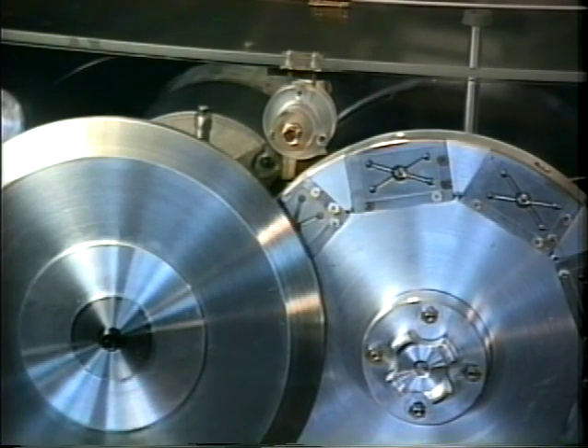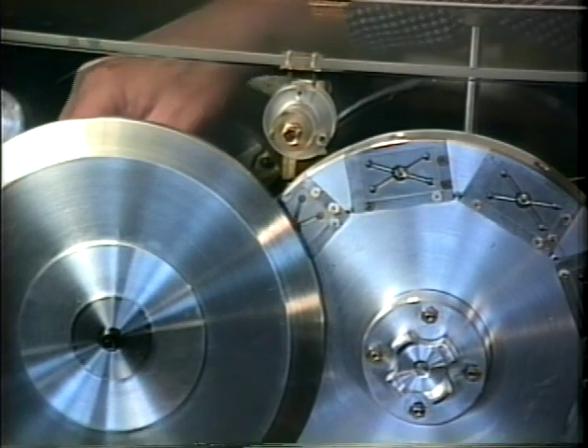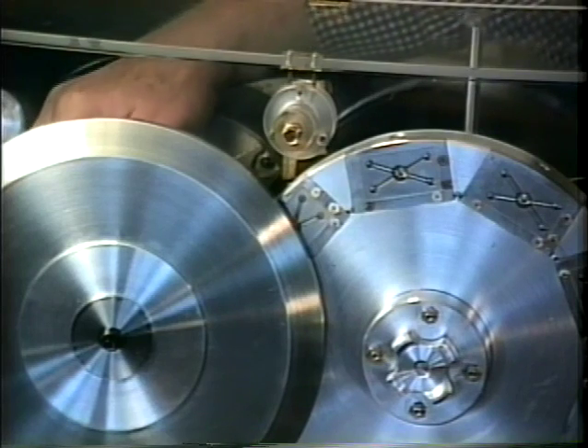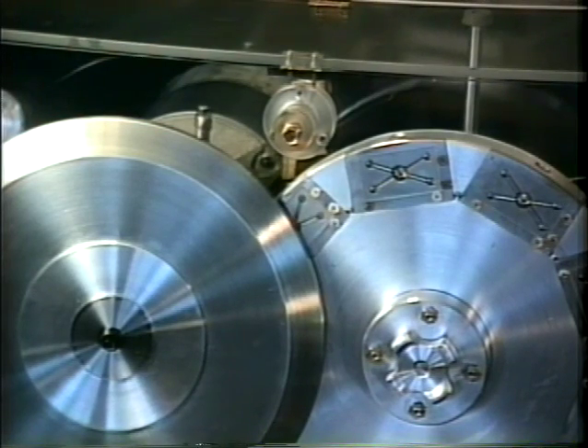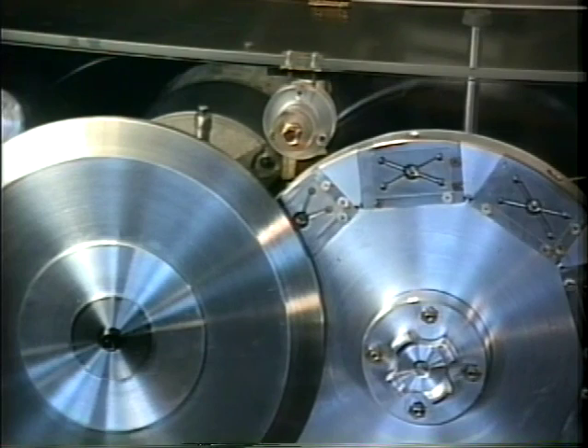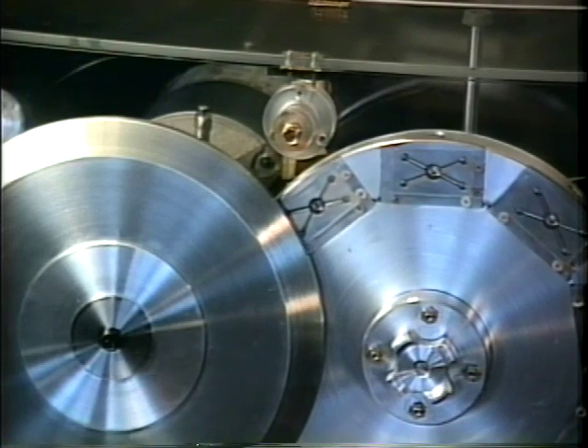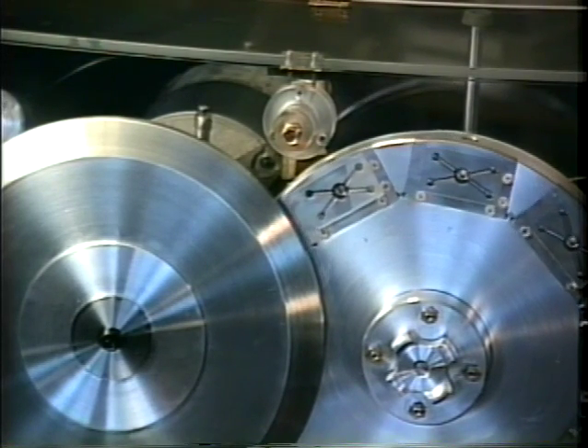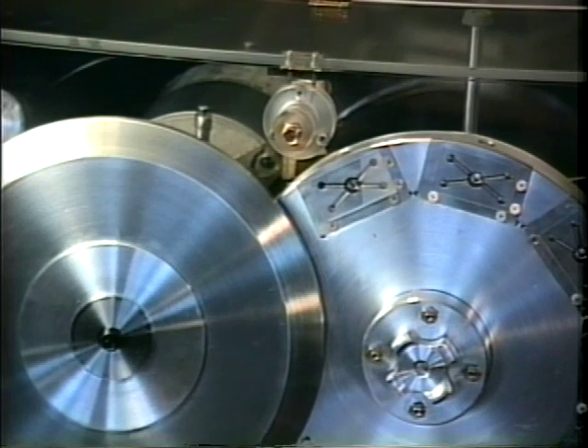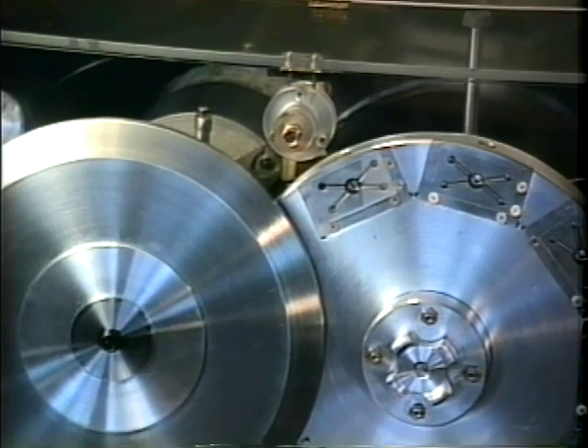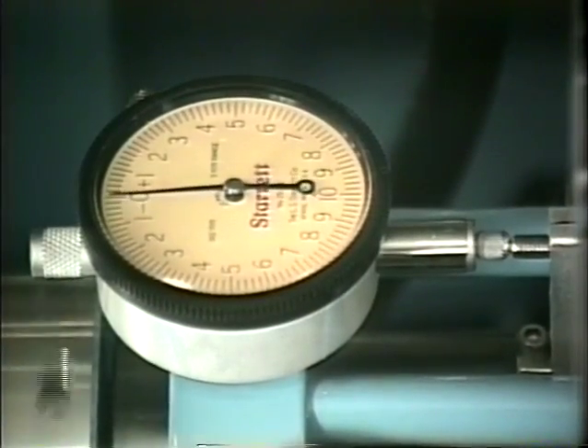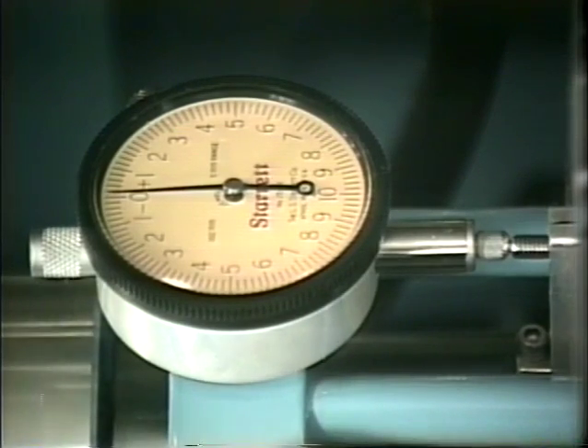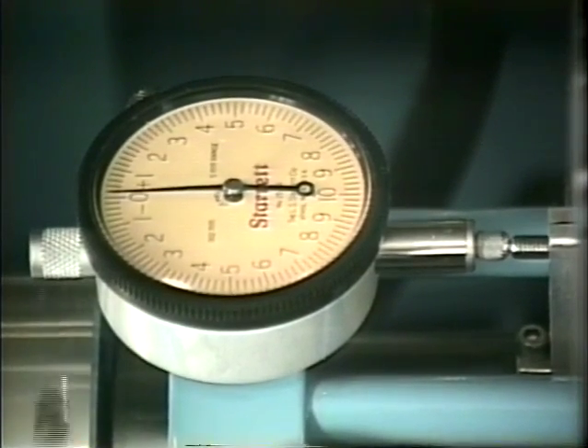Once the dial indicator has been calibrated, then we back the dial indicator away from the slide slightly and then bring the glass slide out from behind the diamond plate. And at this point we can set up the machine for grinding glass slides. Usually when grinding glass slides we take off 60 microns. So we'll move the micrometer.